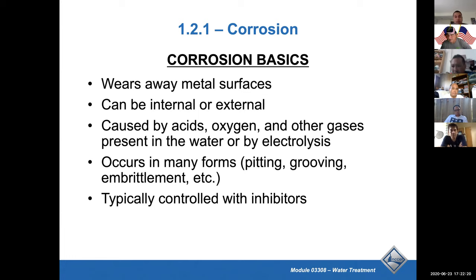And then the next thing is corrosion. Okay, wears away your metal surfaces, can be internal or external. I don't have a picture. I wish I had a picture of my piping at my building. We actually had a lot of external corrosion when we had old fiberglass insulation, and it was wet for a long period of time, and it was actually corroding the pipes from the outside in. So if you look at the pipe, the inside of the pipe is perfectly clean from the chill water treatment, but then the outside of the chill water pipe is all corroded from the galvanic corrosion that was happening because they were sitting in water all the time. And we have black pipe, that's why. So that's why it says corrosion can be internal or external here on the second thing. It's caused by acid, oxygen, other gases.